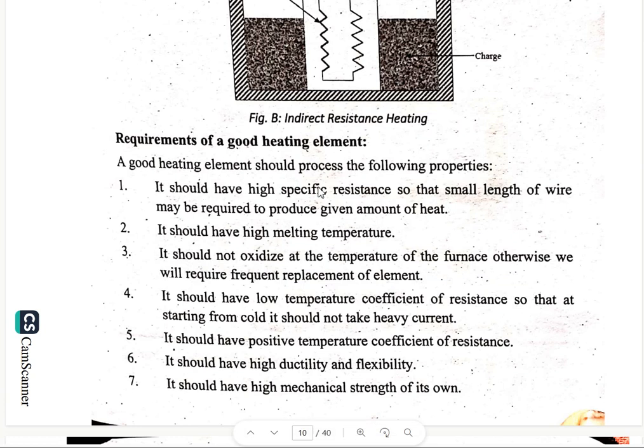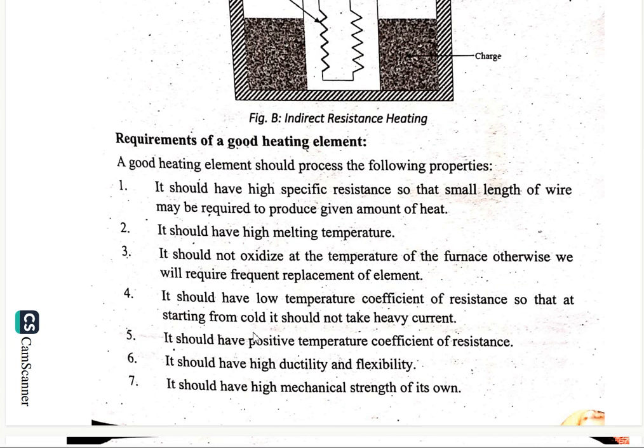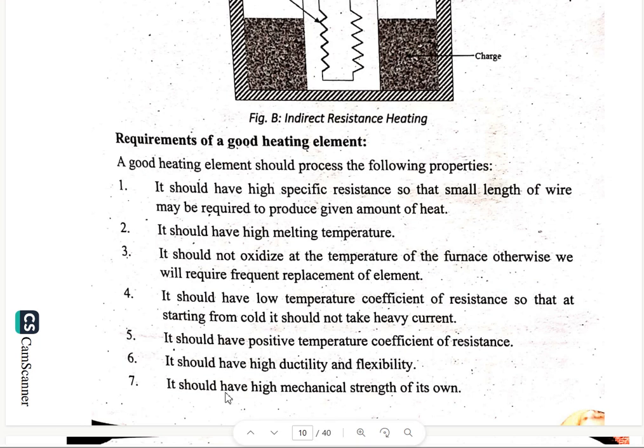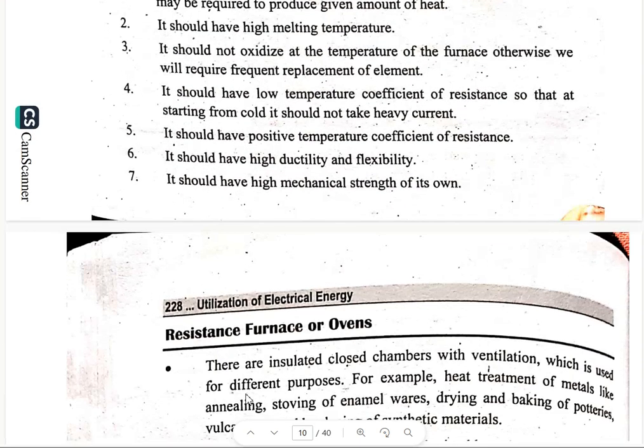For a good heating element, it should have high specific resistance so that a small length of wire may be required to produce a given amount of heat. It should have a high melting temperature, and it should not oxidize at operating temperature, otherwise frequent replacement would be needed. It should have a low temperature coefficient of resistance so that starting from cold it does not take excessive current. It should also have a positive temperature coefficient of resistance, high ductility and flexibility, and high mechanical strength.